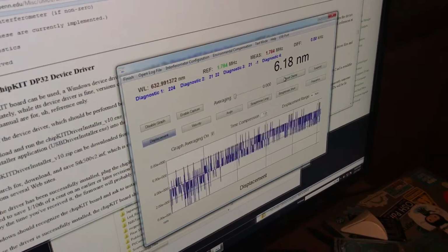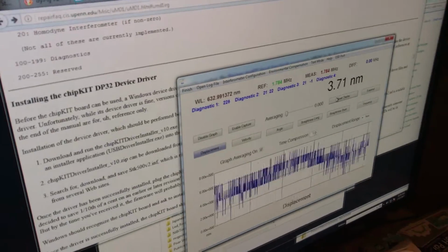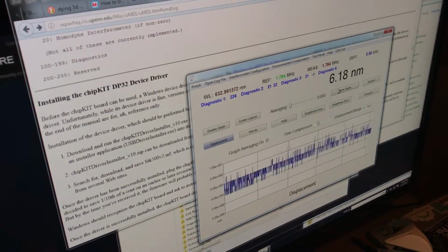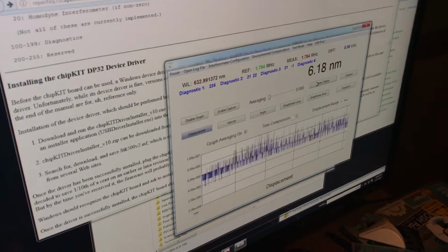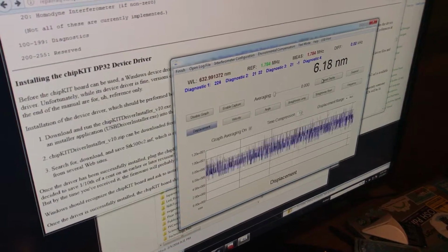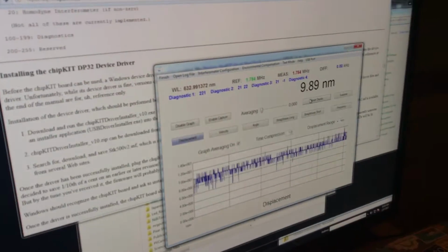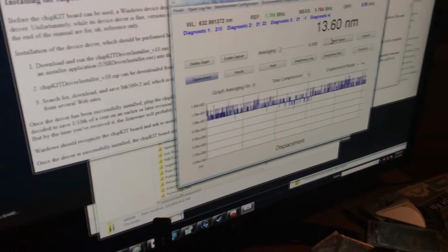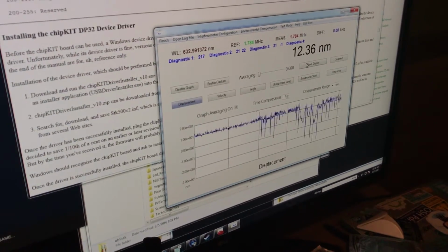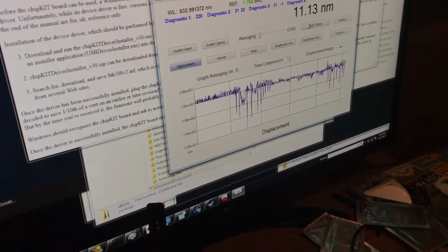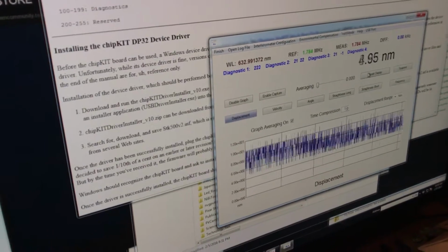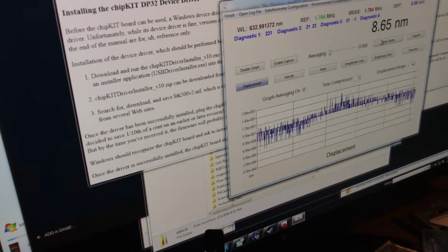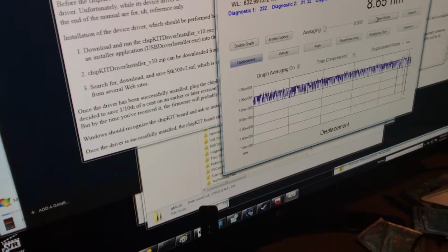The measurement mirror is just taped to the interferometer at the moment, so there shouldn't be any motion at all. But you'll be getting some motion because of vibration. This is on an anti-vibration table, but the anti-vibration table isn't turned on. The mirror is just taped down, so I don't expect it to be too stable, and I'm not sure I've really done the alignment, but you can see if I just bang the table, I'm getting deflections caused by just vibration.